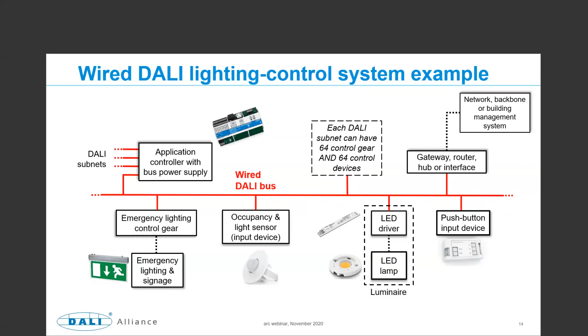You have the input devices. These are providing information to the system. So occupancy and light sensors and push devices are some examples, but you can also get other analog and digital input devices. Each DALI subnet can have 64 pieces of control gear and 64 control devices on the same bus. So that's the limitation for one bus, but of course you can have multiple buses on even one controller and then multiple controllers in a system. So that's how you would build a DALI system to be building wide or multi-building wide.